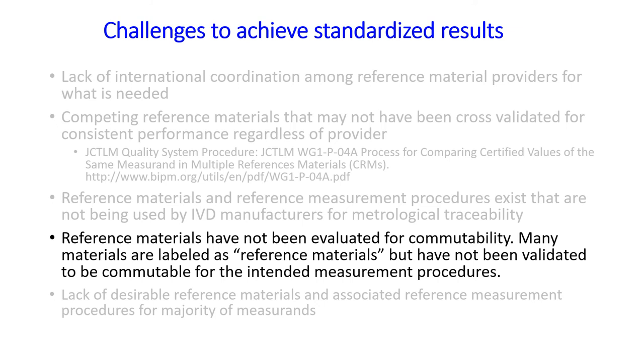Lack of validated commutable reference materials is the most significant challenge impacting efforts to achieve standardized laboratory results. Higher-order matrix-based reference materials that are not commutable with clinical samples make them unsuitable for use in calibration hierarchies and may even contribute to non-comparable results if applied inappropriately or with inadequate validation. Dr. Miller will cover commutability in more detail as part of his presentation.